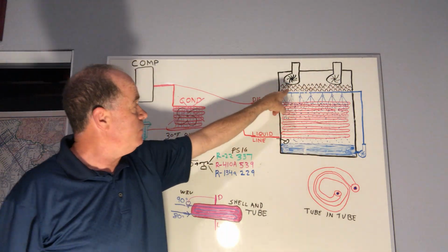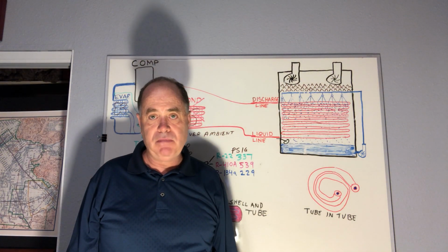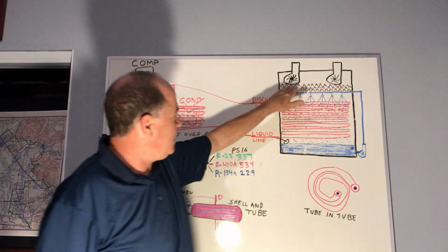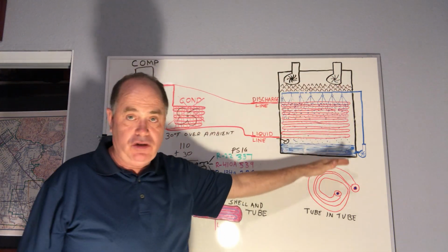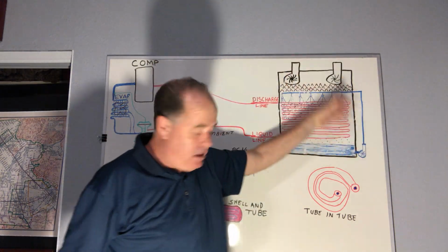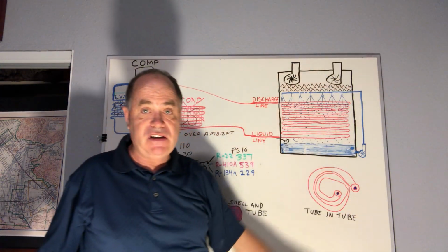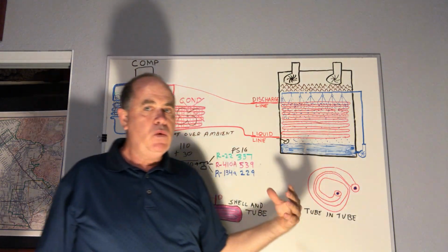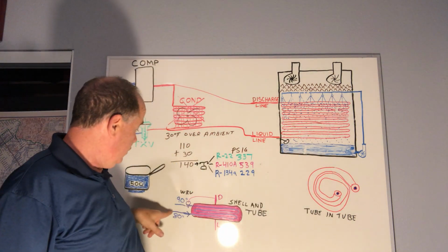Now, up here we have what's known as eliminators, just like the ZZ Top album, and you might want to look up that video or images. It's pretty cool. Eliminators. When the water gets too warm, the fans come on and draw in more air through our louvers, and more water evaporates, causing the temperature to drop. So even for a cooling tower or an evaporative condenser, we maintain the water temperature with a thermostat that says, okay, this is 80 degrees.